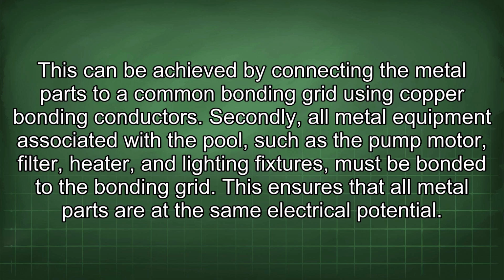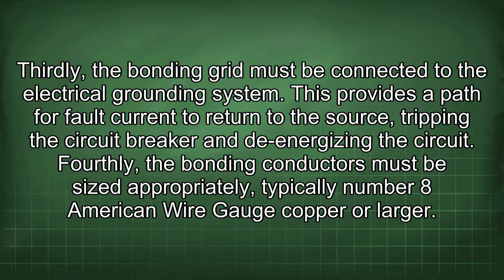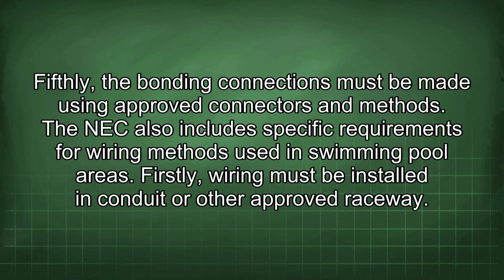Secondly, all metal equipment associated with the pool, such as the pump motor, filter, heater, and lighting fixtures, must be bonded to the bonding grid. This ensures that all metal parts are at the same electrical potential. Thirdly, the bonding grid must be connected to the electrical grounding system. This provides a path for fault current to return to the source, tripping the circuit breaker and de-energizing the circuit. Fourthly, the bonding conductors must be sized appropriately, typically number 8 American wire gauge copper or larger. Fifthly, the bonding connections must be made using approved connectors and methods.